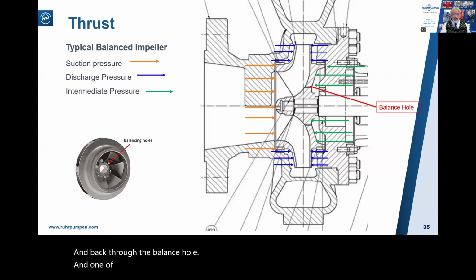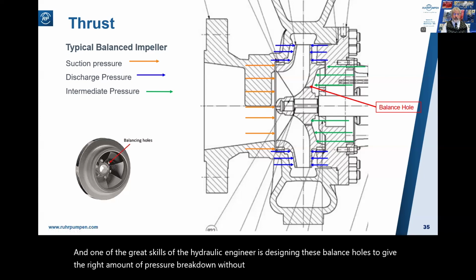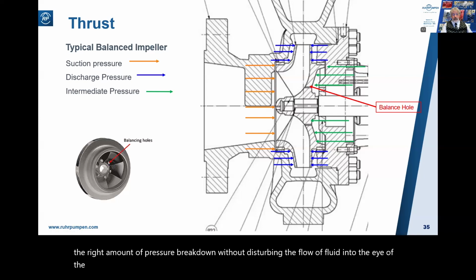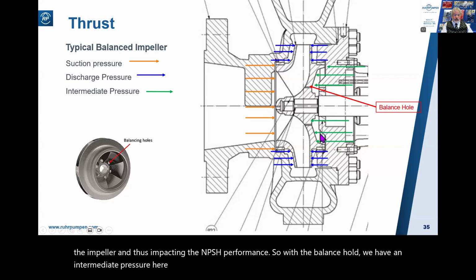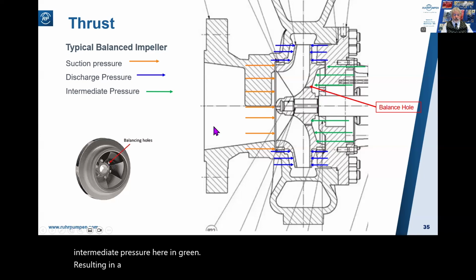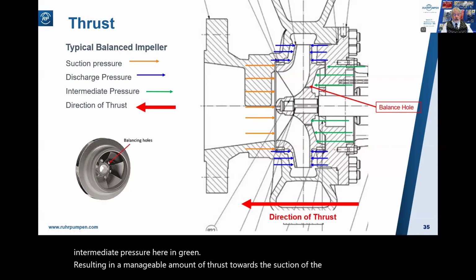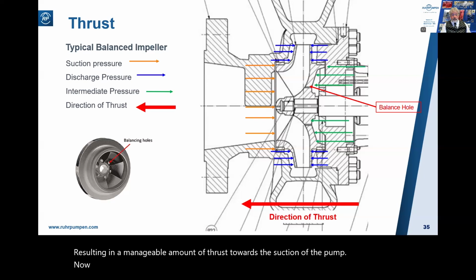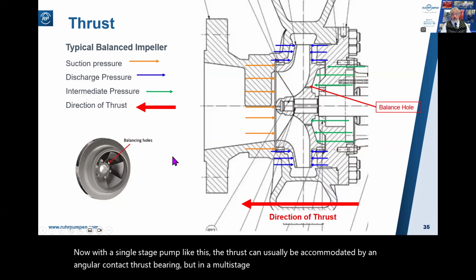And one of the great skills of the hydraulic engineer is designing these balance holes to give the right amount of pressure breakdown without disturbing the flow of fluid into the eye of the impeller, and thus impacting the NPSH performance. So with the balance holes, we have an intermediate pressure here in green, resulting in a manageable amount of thrust towards the suction of the pump. Now, with a single stage pump like this, the thrust can usually be accommodated by an angular contact thrust bearing. But in a multi-stage pump with, say, 10 impellers, that thrust can be considerable.